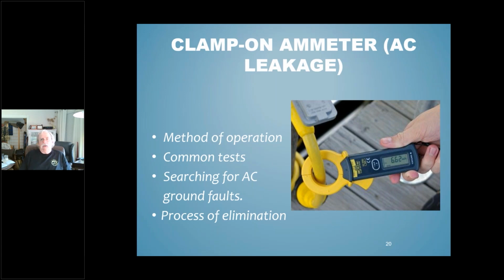But all that said, international standards only allow for very, very low levels of ground fault leakage back into the system. 1 milliamp, maybe 2 milliamps, no more than that, per appliance. So it's not going to be an issue. That's where the 30 milliamps came from. We know that depending on the size of the boat and how much equipment is installed, getting upwards of over 20 milliamps of leakage current is conceivable, but it's not necessarily indicative of a problem. So you need to be aware of that as well.